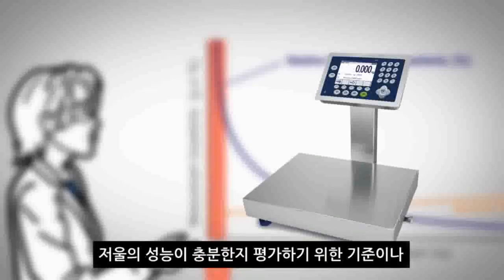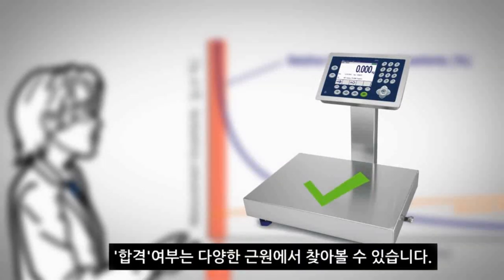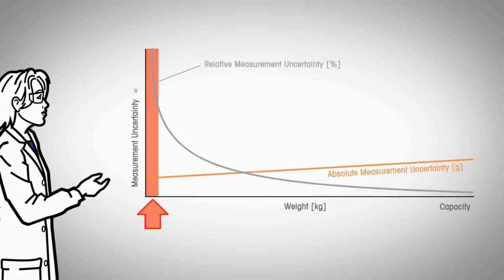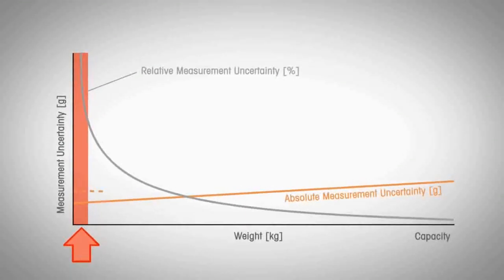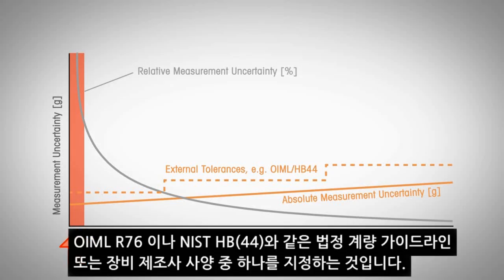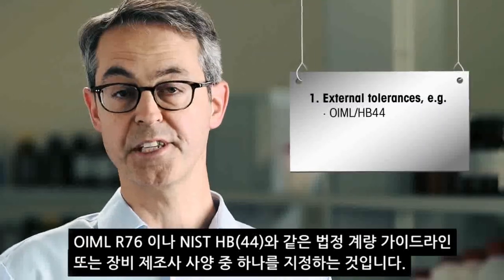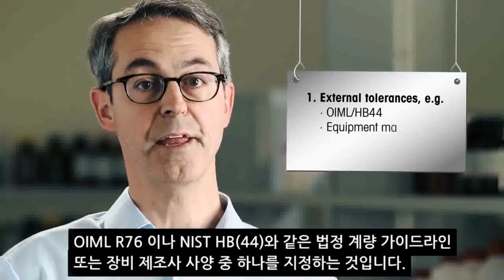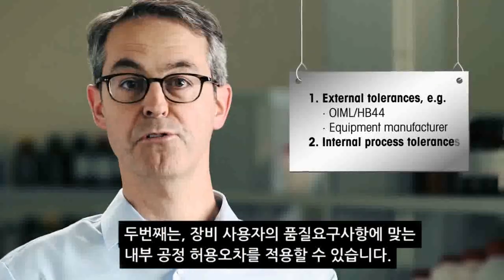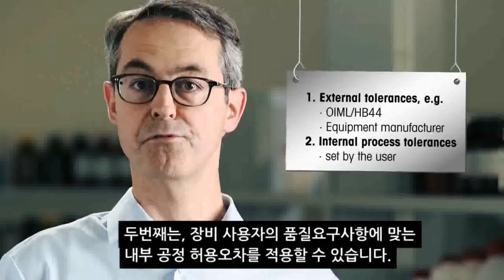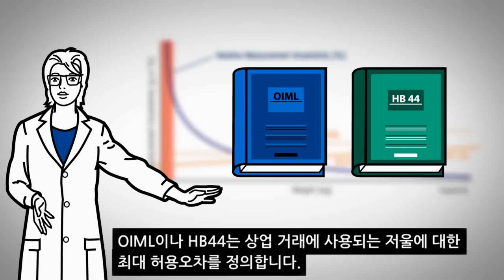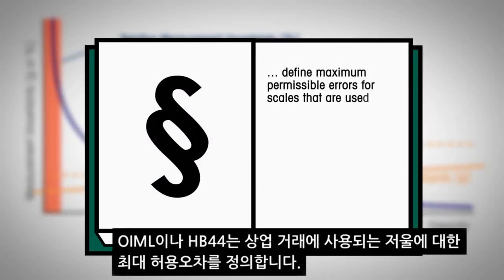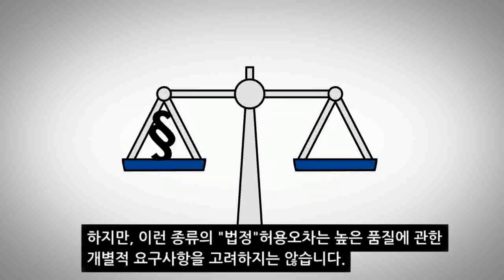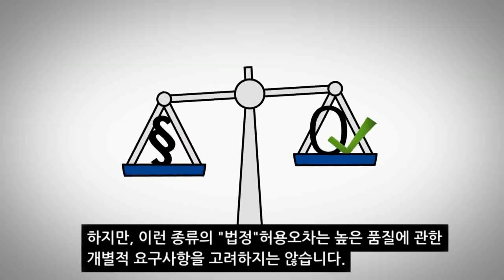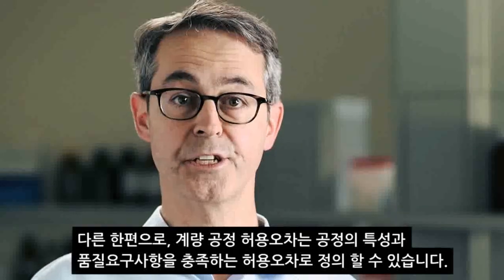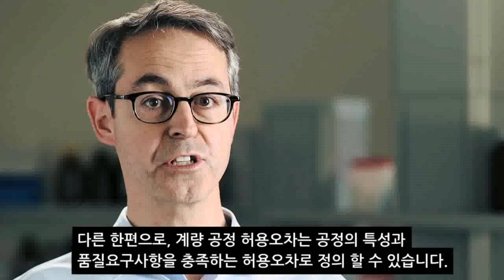The criteria for assessing whether a balance or scale performs good enough or passes comes from a variety of sources. You can distinguish between two types of tolerances. First are external tolerances, specified either by legal metrology guidelines such as OIML R76 or NIST Handbook 44, or by the equipment manufacturers themselves. Second are internal process tolerances, set by the quality requirements of the equipment users. OIML or Handbook 44 define maximum permissible errors for scales that are used in commercial transactions. However, their legal tolerances do not consider your individual requirements for high quality. Process weighing tolerances, on the other hand, are defined by you to meet your specific process and quality requirements.